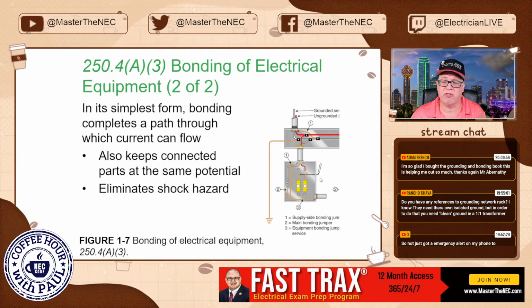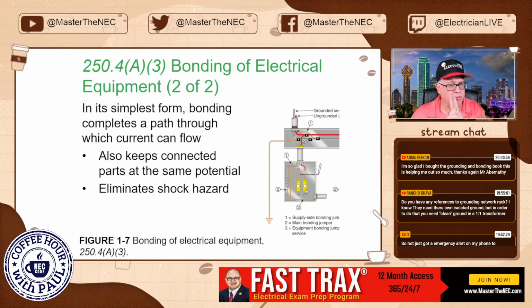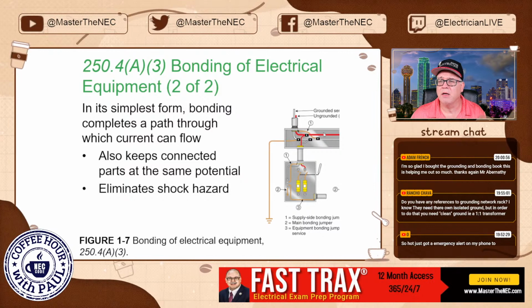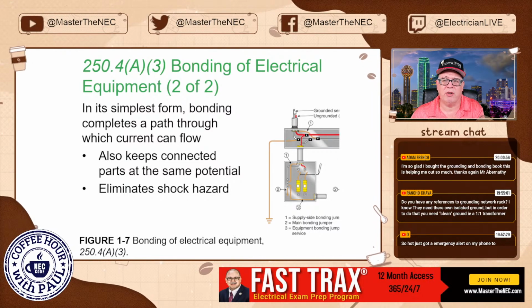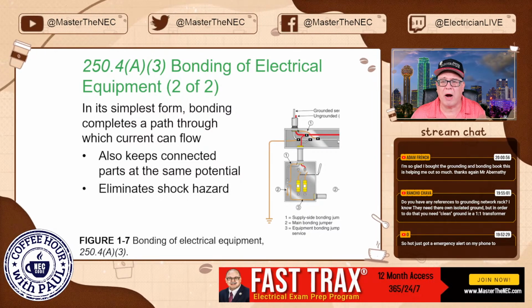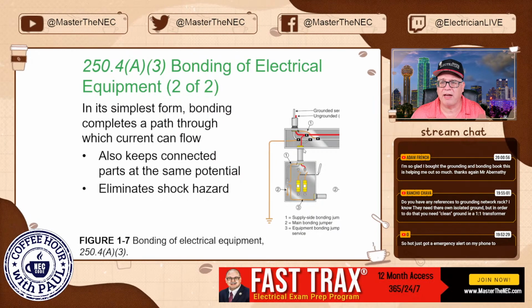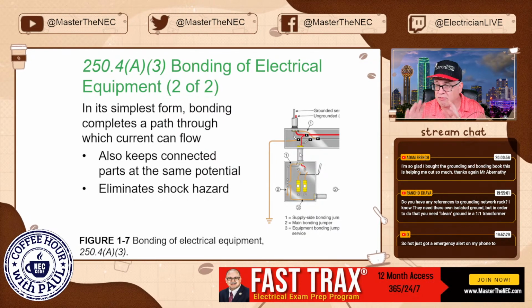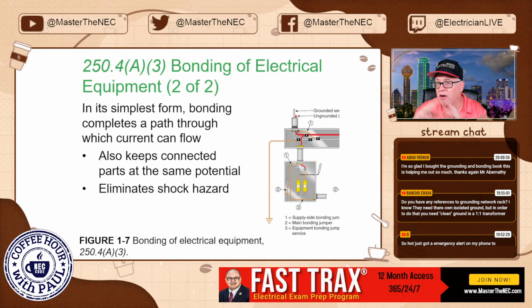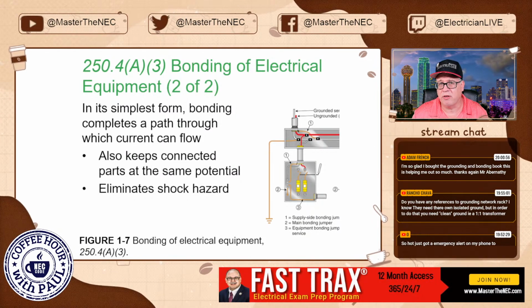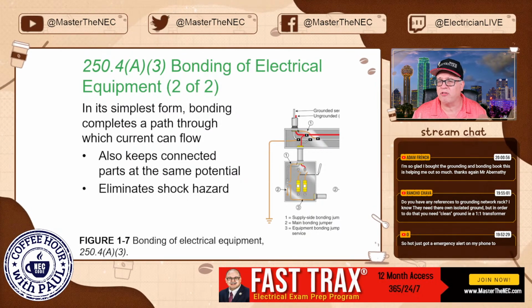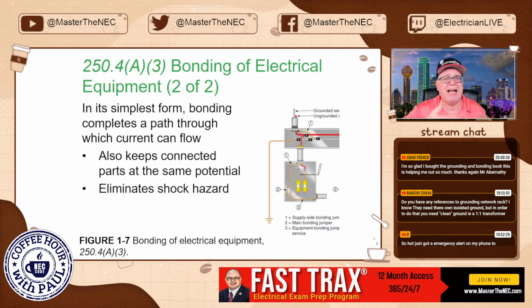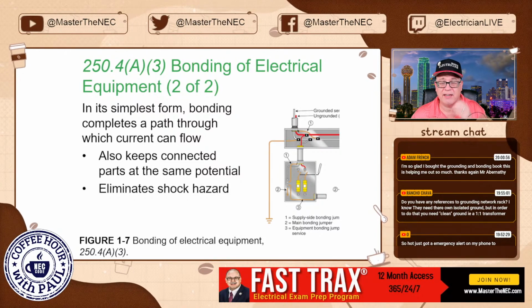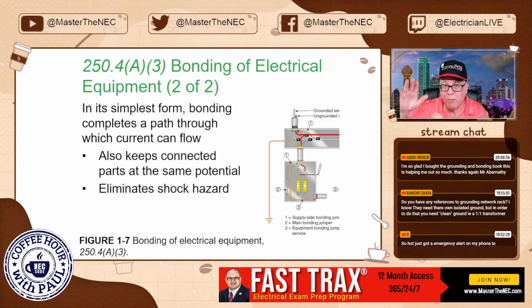Now, you'll notice in this illustration that we have two services grouped in the same location. We've got our ungrounded hot conductors, and our grounded conductor comes down into a wireway. And then, of course, you have these. These aren't feeder taps. They are taps. You're permitted to tap service conductors. In fact, we have rules in the code in 230.82 about what can be on the supply side of a service disconnect, which at some point we'll probably get to.